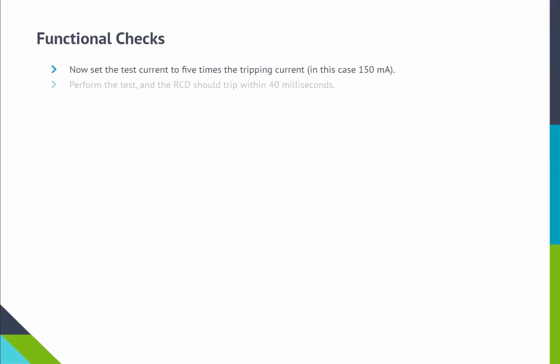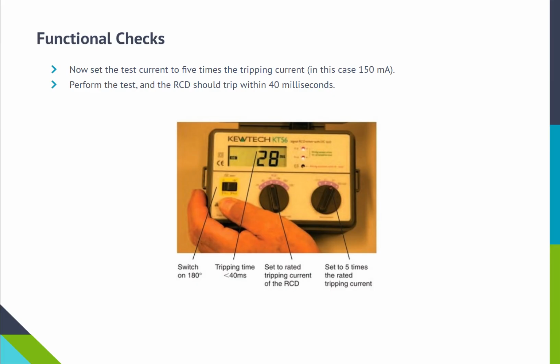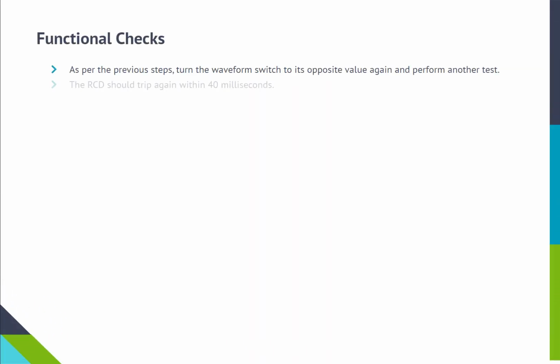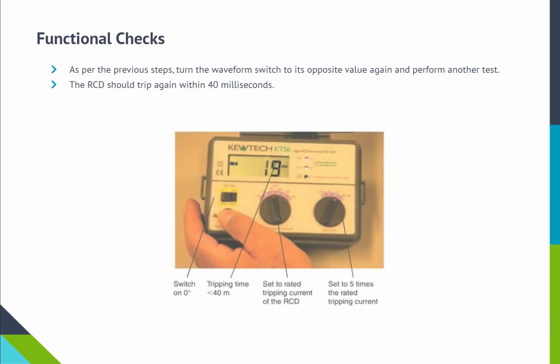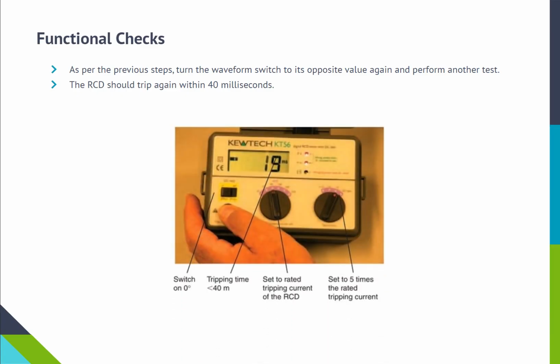Now set the test current to 5 times the tripping current, in this case 150 milliamperes. Perform the test, and the RCD should trip within 40 milliseconds. As per the previous steps, turn the waveform switch to its opposite value again, and perform another test. The RCD should trip again within 40 milliseconds.